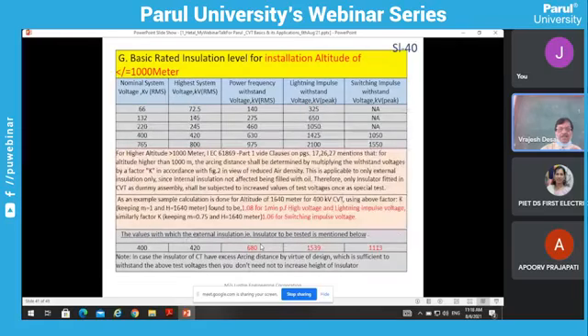Now coming to the last item, the basic rated insulation level. This level is applicable up to an altitude of 1,000 meters, that is, less than 1,000 meters height. For example, for 400 kV, the highest system voltage is 420 kV. Power frequency withstand voltage is 630 kV. Lightning impulse is 1425 kV, that is always in peak, and switching impulse is 1050 kV.